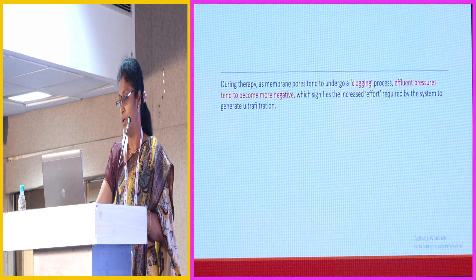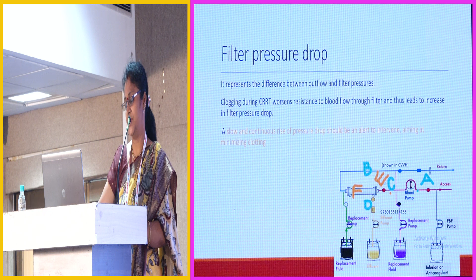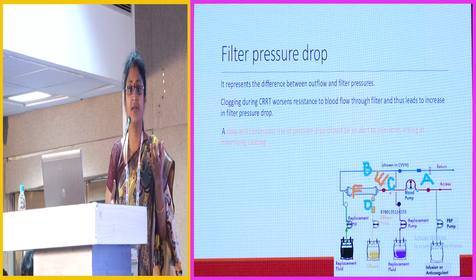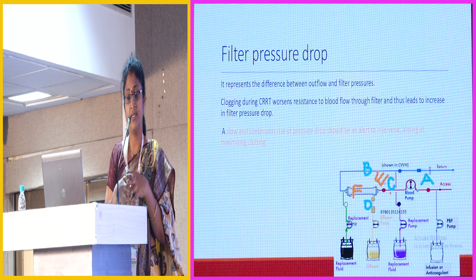This is another term, the filter pressure drop. That is E. The filter pressure drop is between the filter pressure and the outflow pressure. A slow and continuous rise of the pressure is an alert to intervene, aiming at minimizing the clotting. So two more points. If the rise of the filter pressure is very slow, suspect clogging or fouling, whatever we call it. Suppose the rise is sudden and dramatic, then you suspect some clot in the catheter, or some sudden event in the catheter and filter, so that you have to change the filter immediately.